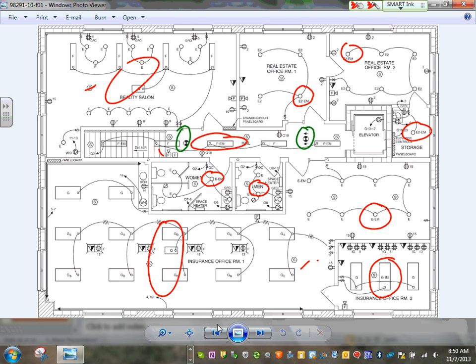Mechanical rooms, we also like to have one. If we have an air handling unit running and you are working on it, and all of a sudden the power went off, it's dangerous, right? So you have to have one in mechanical rooms. Bathrooms: you're sitting in the bathroom doing your own business and the power went off, right? If you're like Chad, you'll panic. So they want to put an emergency light in the bathroom and mechanical rooms. Think about any area where people can panic. Hallways need an emergency light.